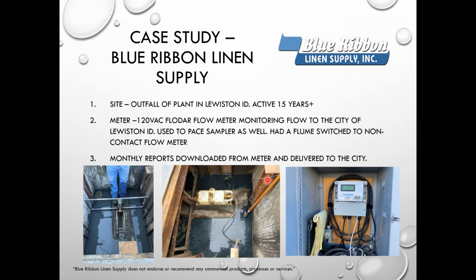Blue Ribbon Linen Supply. We've worked with these guys for probably over 15 years. They had an open vault where they actually had a flume and weir at one point. They were able to take the flume and weir out and modify it to where it's just an open pipe channel here. Of course, they get a lot of storm runoff and that type of stuff that sits down here in the sides, where we were talking about filling that back up with concrete so that they don't have the stagnant water. But that is pretty much the stagnant water that sits around the side there, and so it reads velocity and level in that pipe.